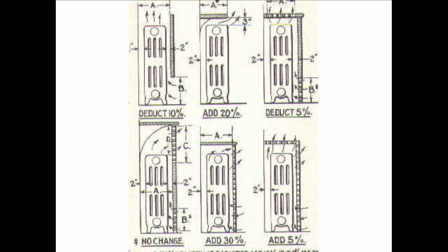People that sell these radiator enclosures nowadays talk about how this improves the efficiency of the radiator. Well, it does if the radiator is oversized. I mean, it's got to cut down 30% of the heat that you have in the room. So that's why it appears to improve the efficiency.